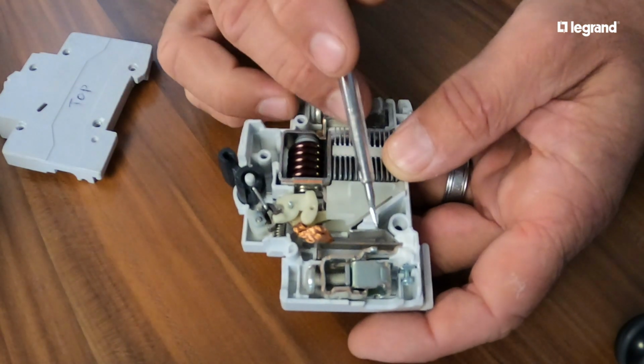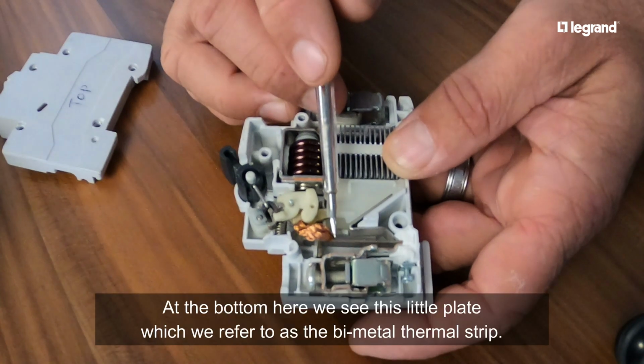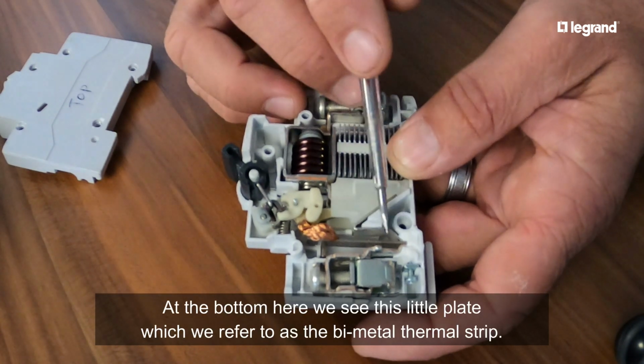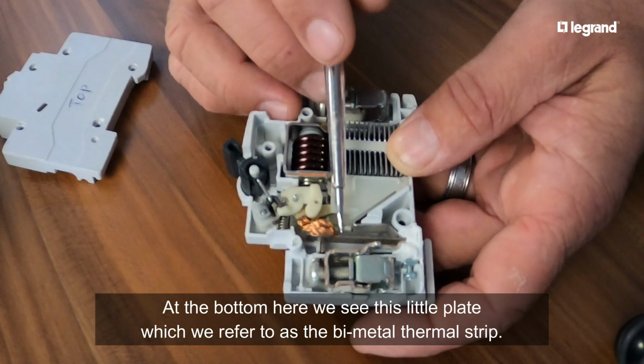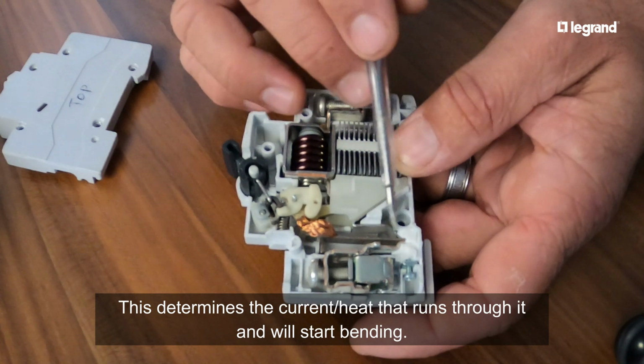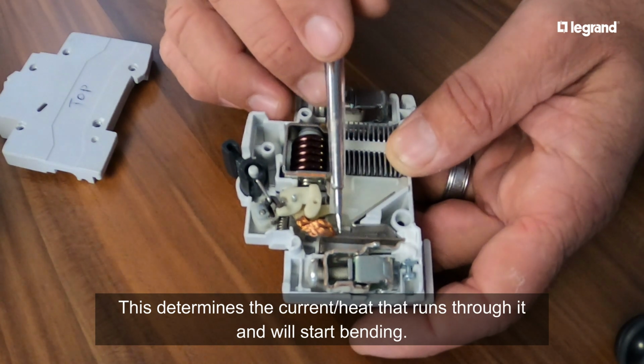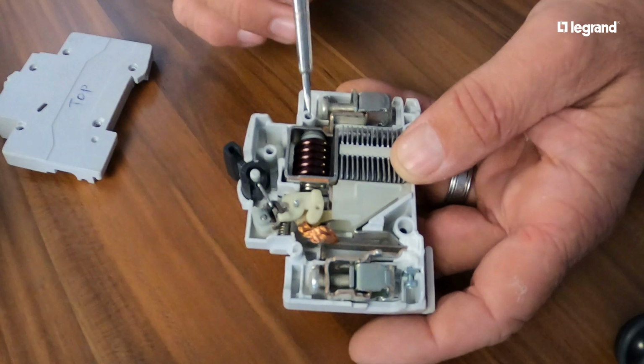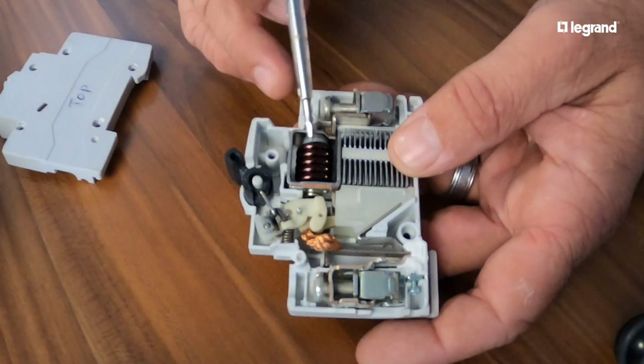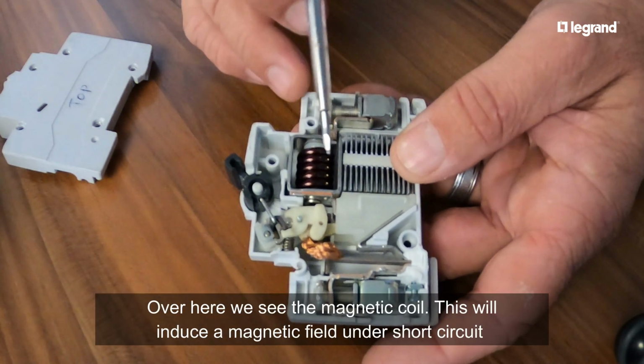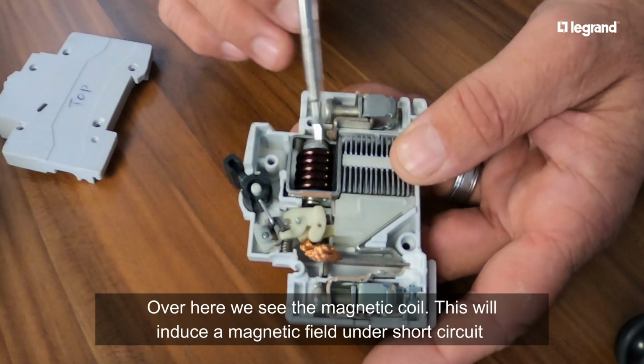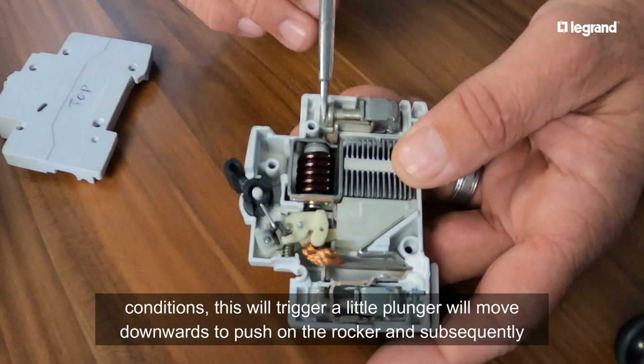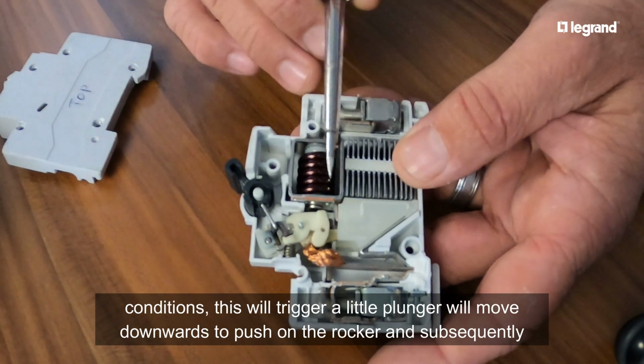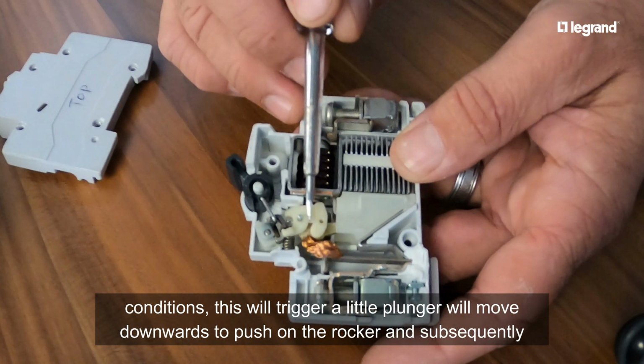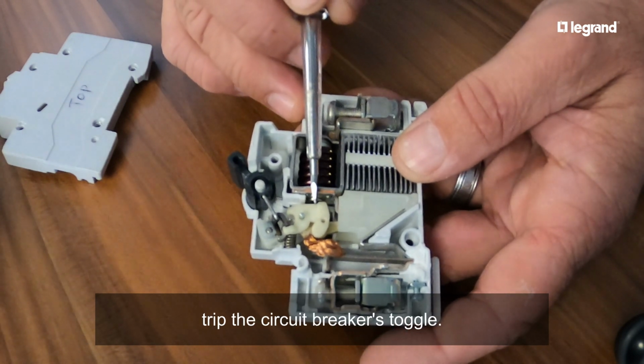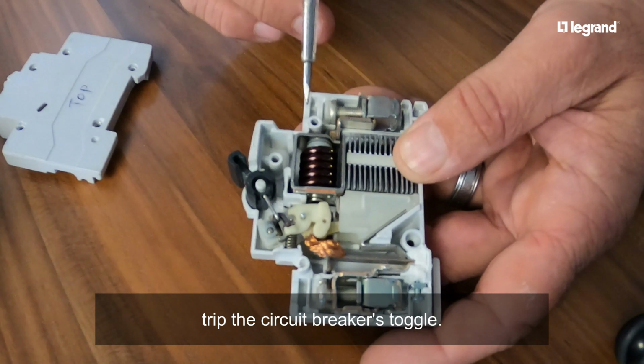Then at the bottom here, you'll see this little plate. This is the thermal strip, called a bimetal, that will determine the current that runs through it. It will start bending. I'll show you now how it trips. And then over here, we've got the magnetic coil. This will induce a magnetic field under short circuit conditions. A little plunger in the middle will then move down. This little guy here is the rocker. Once we push on this, it will trip the circuit breaker's toggle.